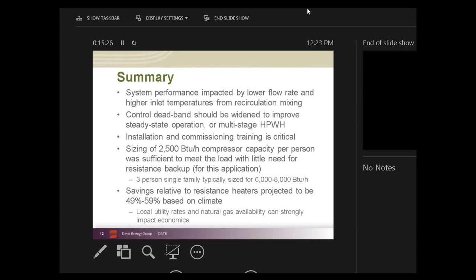So the unit was sized properly to meet the load. There was very little electric resistance usage. And it fits with some of the normal recommendations for single-family homes. And finally, the savings are most significant in areas where electric costs are higher than natural gas. And cheap natural gas can prove a challenge with the higher installation costs of these units.